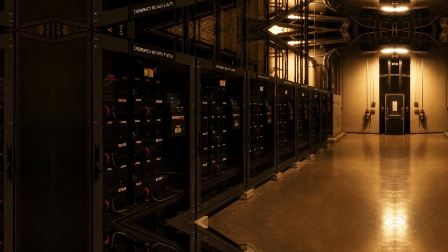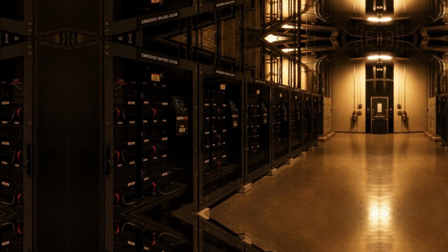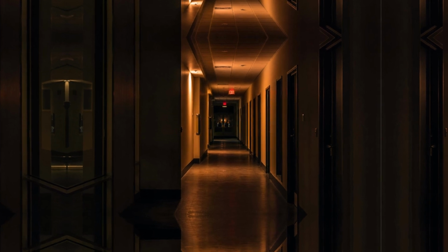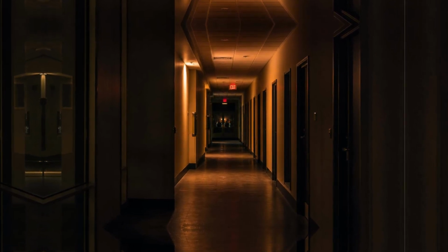The cabinet is the same. The indicator lights on the charger show normal. The voltage under light load appears acceptable. But put that battery under the full demands of an actual discharge, a real emergency, a genuine transfer to backup power, a sustained run at the current levels the system actually requires, and the insufficiency that was invisible during normal operations becomes immediately and consequentially apparent. This is why testing matters so deeply in battery maintenance, not periodic glances, not casual visual inspections, but actual testing, load testing, impedance testing, capacity verification, that exercises the battery under conditions that reveal its true state rather than its apparent one.